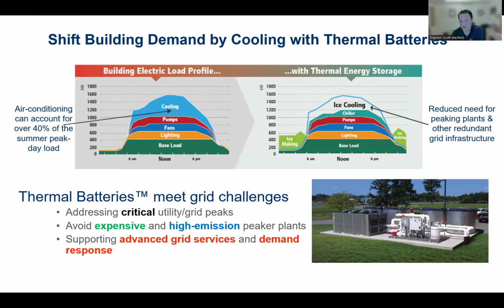So what's traditionally been done is you make ice overnight when rates are low, then melt the ice during the day when rates are higher. This helps reduce peak electricity demand on the grid, flattening out the utility profile and making it easier for utilities to integrate green energy into the grid. This means you don't have to build peaker plants, you can reduce transmission lines, and it supports advanced grid services and demand response.